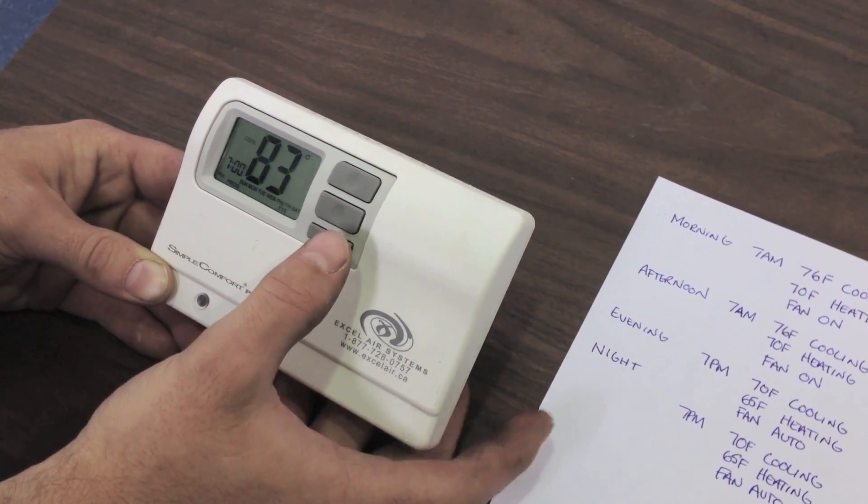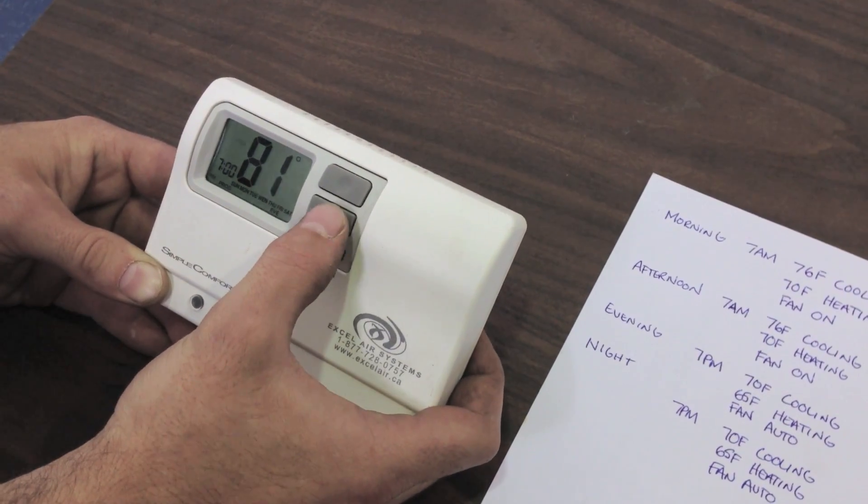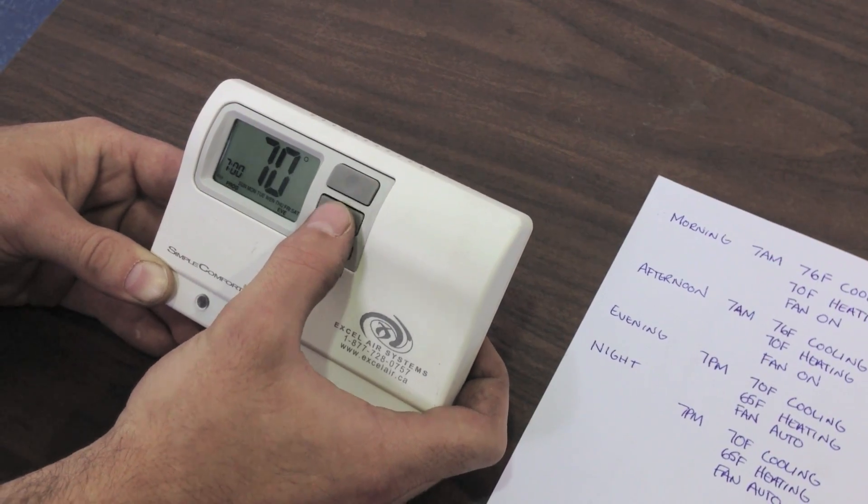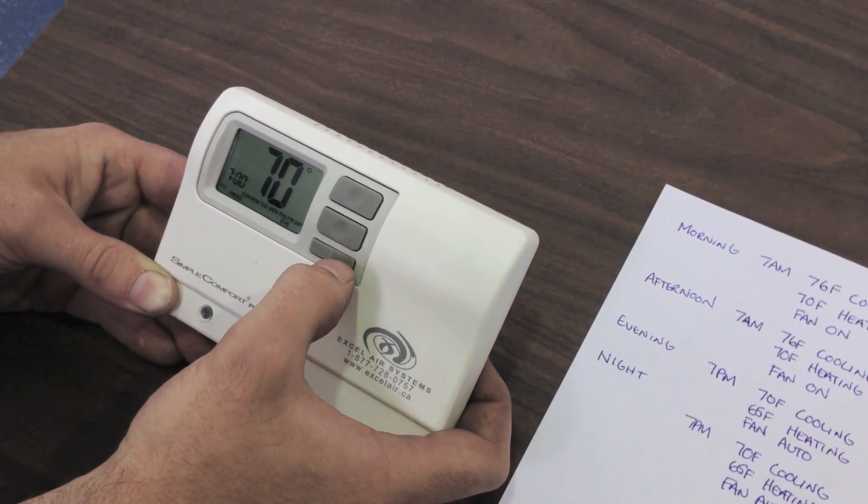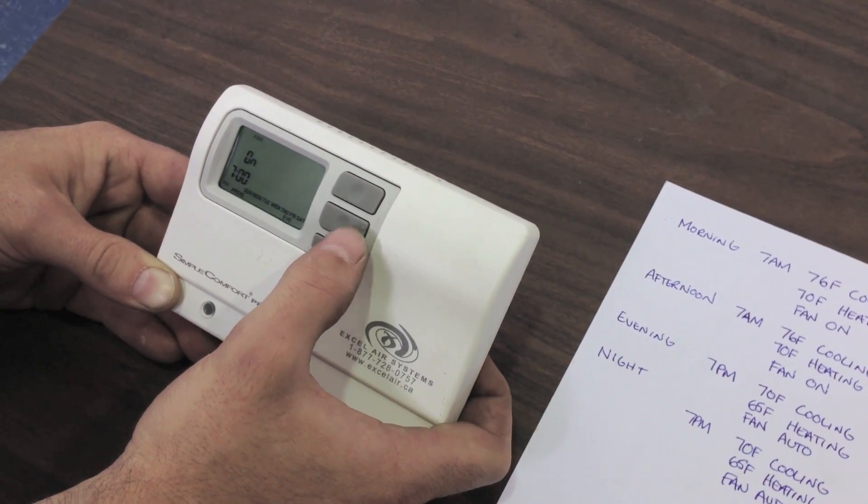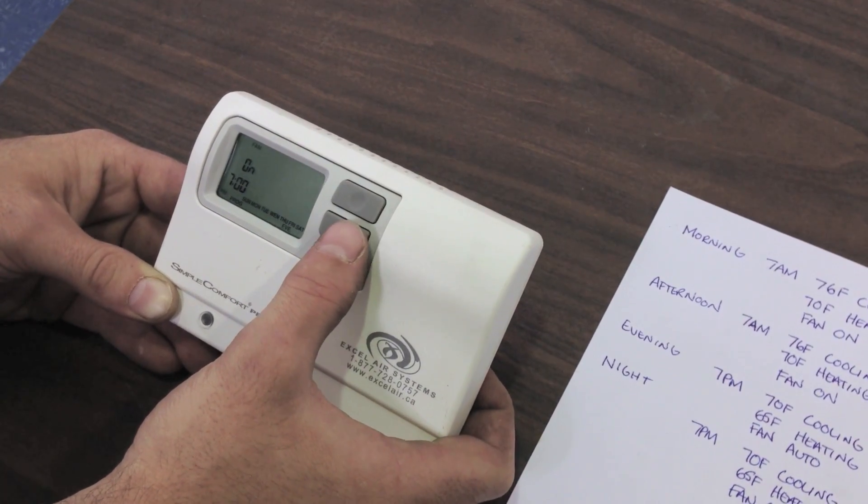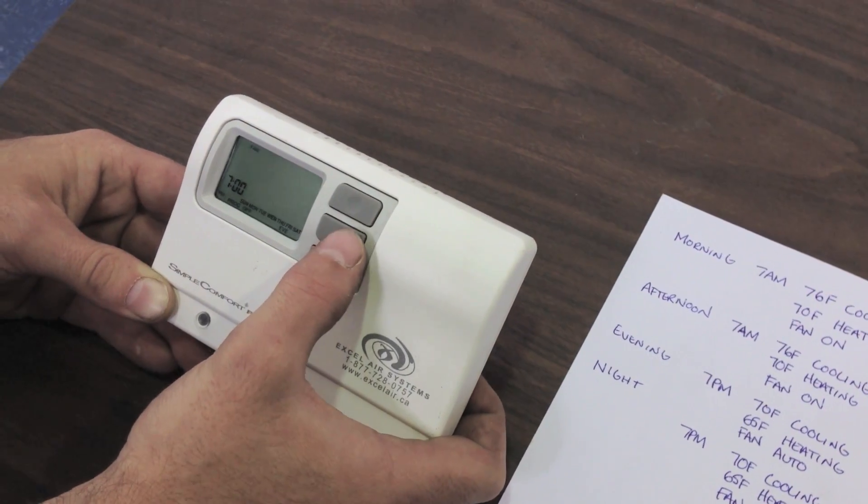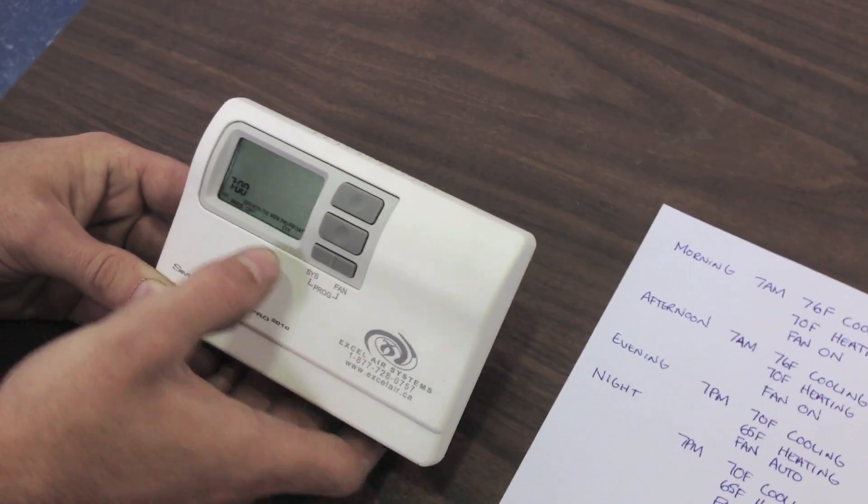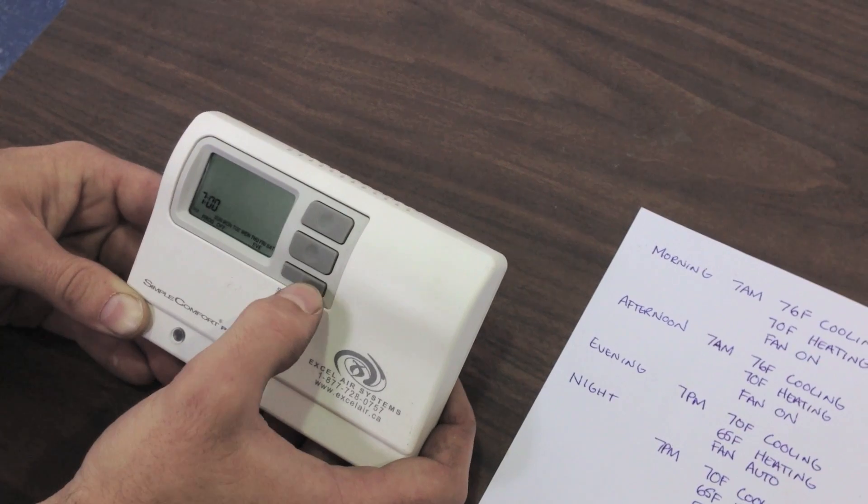Then we have our cool set point, which we want down to 70 degrees. We're going to push the down arrow, get to 70. And then when we're happy, we push fan. And now for our off cycle, we want our fan to turn off when the cooling or heating turns off. So we're going to push our down arrow so the little tiny word off disappears. When we're happy, we push our fan button.